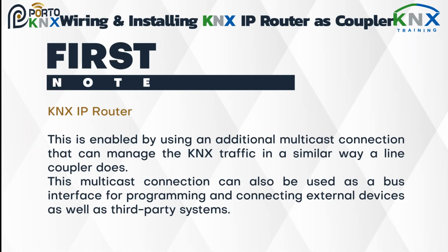This is enabled by using an additional multicast connection that can manage the KNX traffic in a similar way a line coupler does. This multicast connection can also be used as a bus interface for programming and connecting external devices as well as third-party systems.